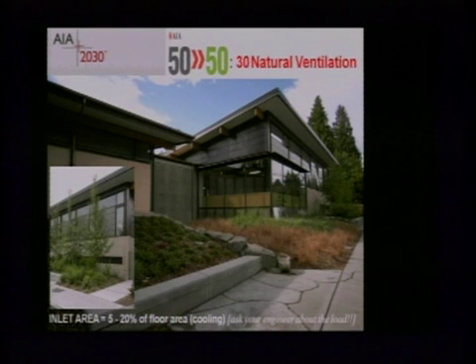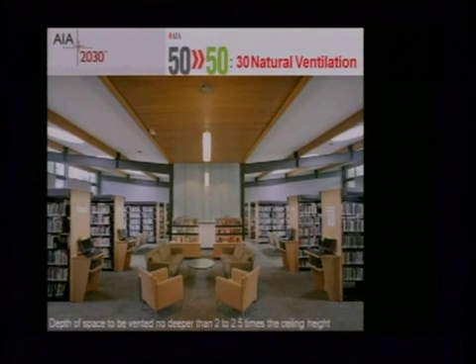We can quite easily ventilate most buildings for fresh air through natural systems during the times of year when the temperature outside is a temperature that you would appreciate inside. So what this session will do is it will give you rules of thumb that will start to allow you to size these aperture areas for ventilation for fresh air. And they'll show you examples of this. This happens to be a Miller Hall building in Northeast Seattle. They'll talk about the depth of penetration of that natural ventilation. For instance, sort of a general rule of thumb is if you have window apertures on the perimeter, you can naturally ventilate about 2 times as deep as that window ventilation aperture is high or off the floor. So again, showing examples for natural ventilation and giving you those rules of thumb that really make you dangerous.